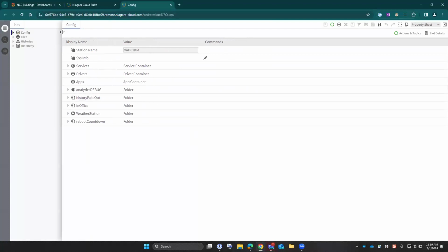what happens, right? Niagara Cloud doesn't set access rights on the actual JACE, right? That's part of Niagara. If I had this plumbed, all my users are local. If I had it plumbed to an LDAP server, it would go and get those users. But we just connect the browser to the actual web service, and then I have to authenticate in there.